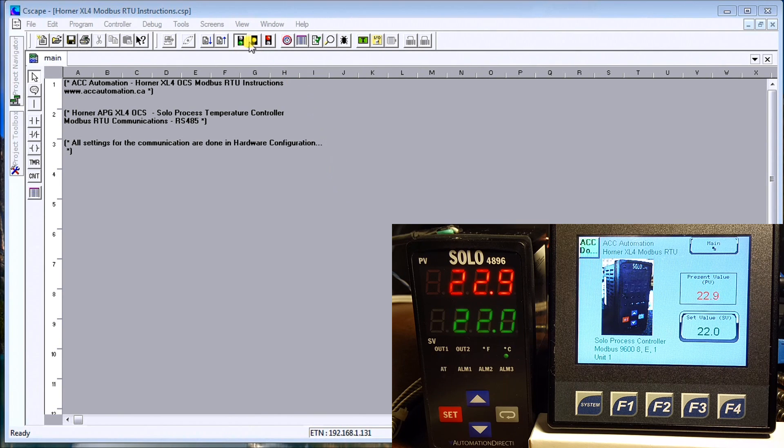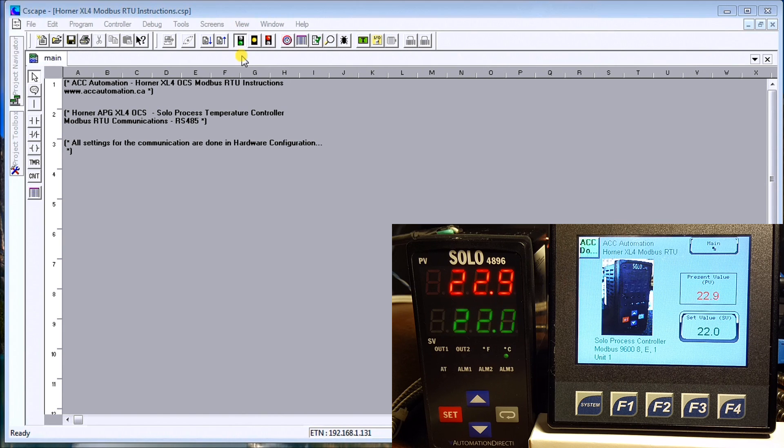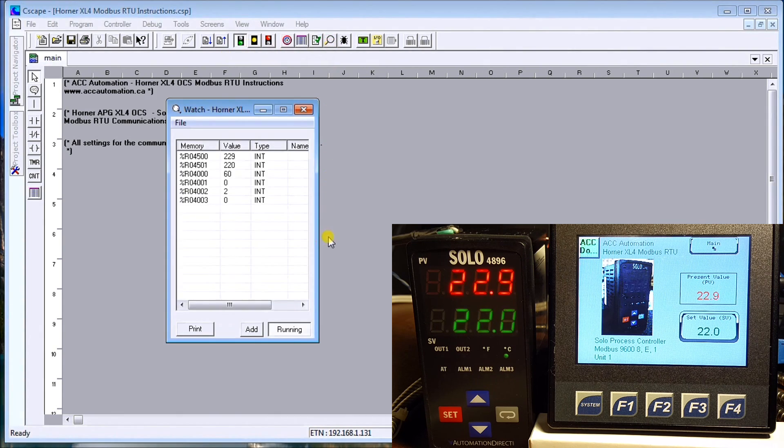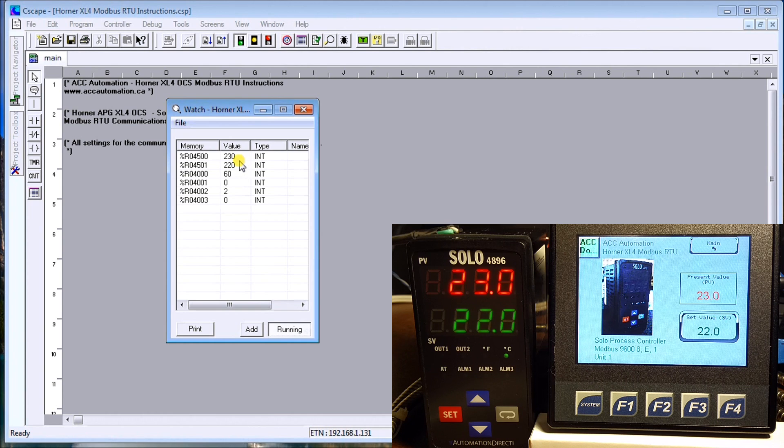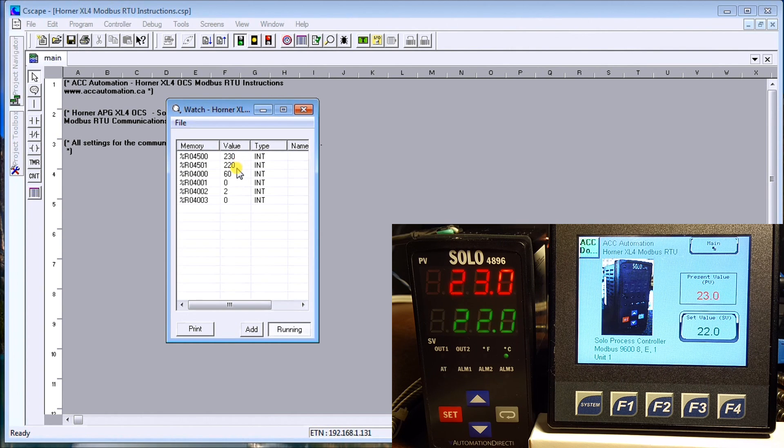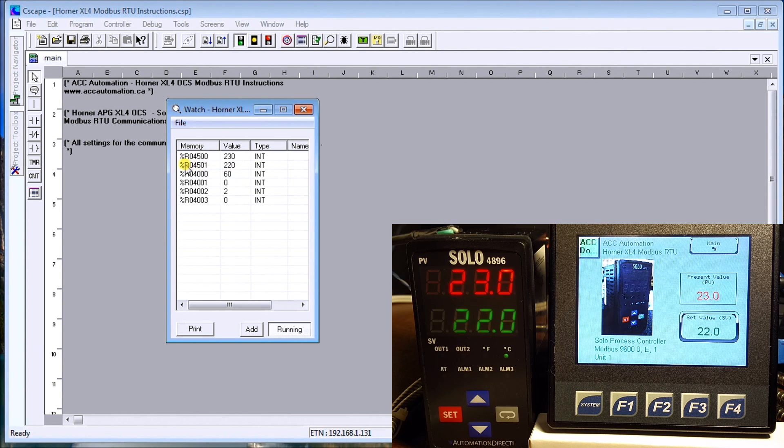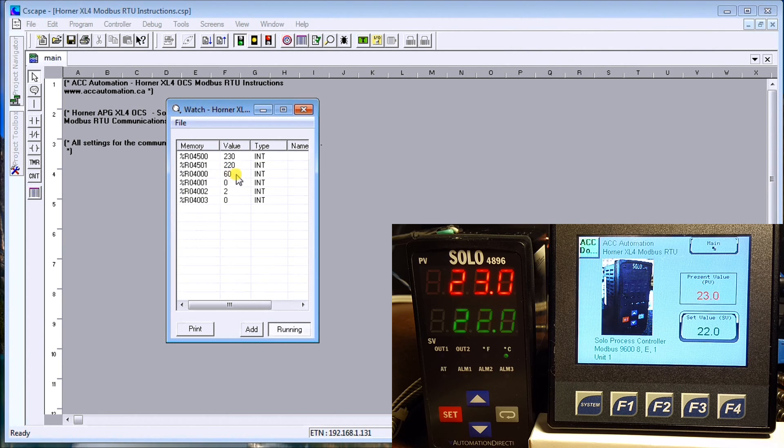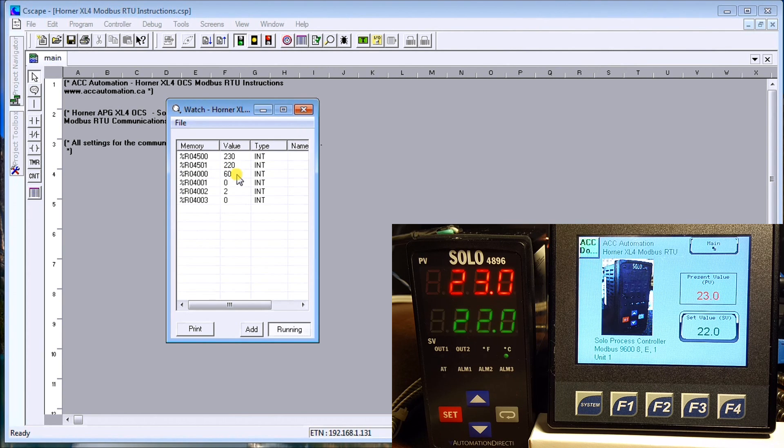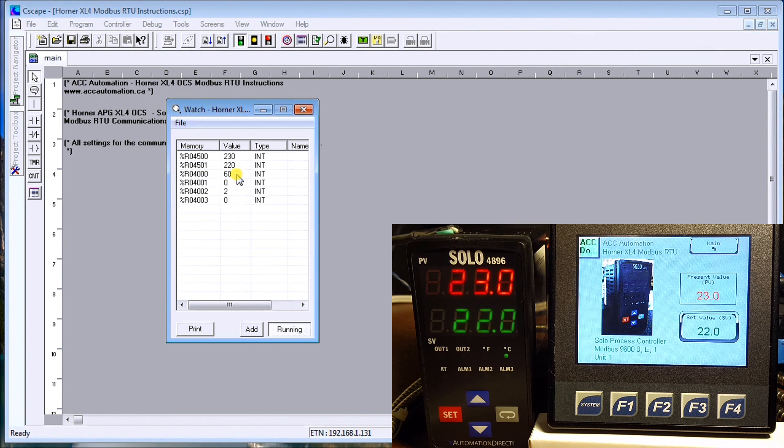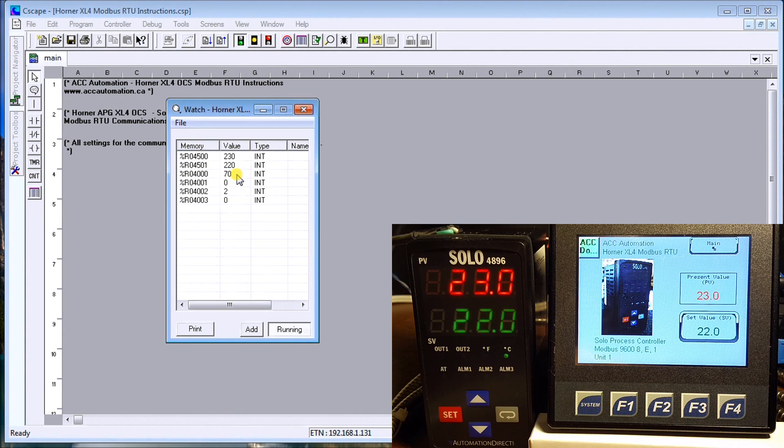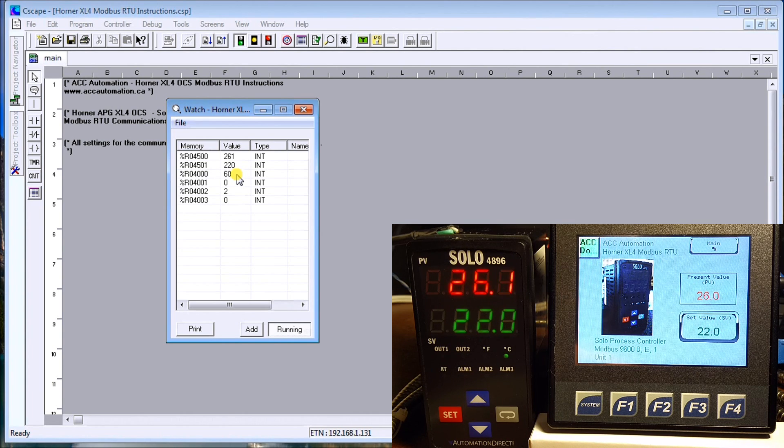As you can see, the set value and present values are actually reading currently right now because I'm in run mode in my controller, and they are updating. My process value is coming in at R4500 at 23 degrees C, and my set value is 22 degrees C. Here's my status which says that we have a current scan time of 60 milliseconds communication between the two. If I hold the thermocouple a little bit, you will see that the temperature will rise and the response rate is pretty good.